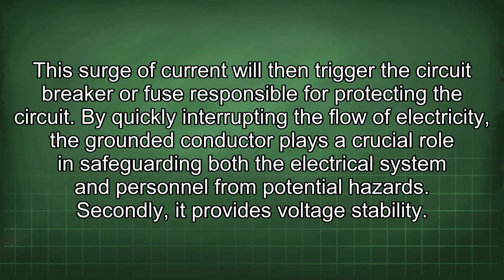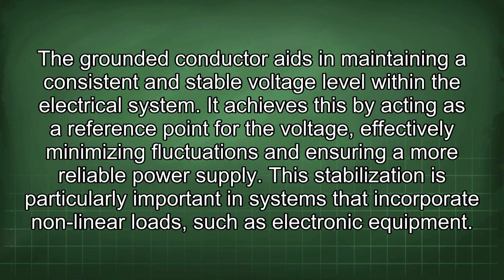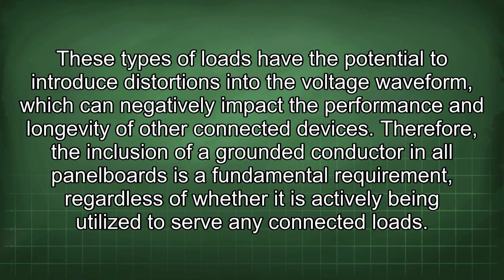Secondly, it provides voltage stability. The grounded conductor aids in maintaining a consistent and stable voltage level within the electrical system. It achieves this by acting as a reference point for the voltage, effectively minimizing fluctuations and ensuring a more reliable power supply. This stabilization is particularly important in systems that incorporate nonlinear loads, such as electronic equipment. These types of loads have the potential to introduce distortions into the voltage waveform, which can negatively impact the performance and longevity of other connected devices.